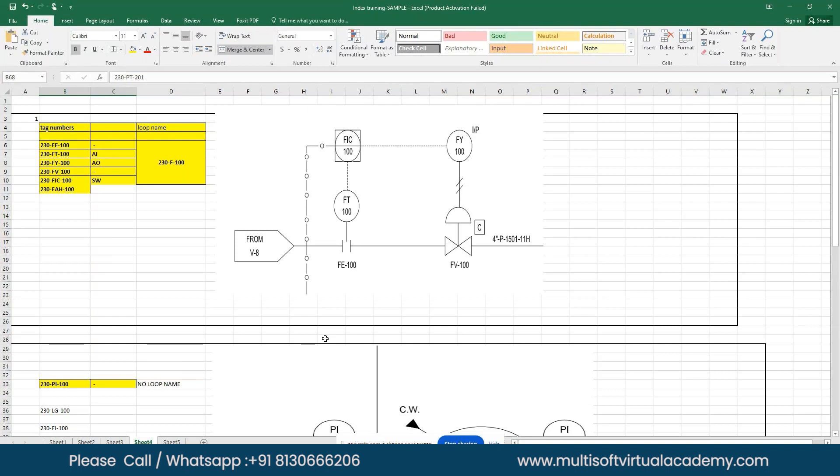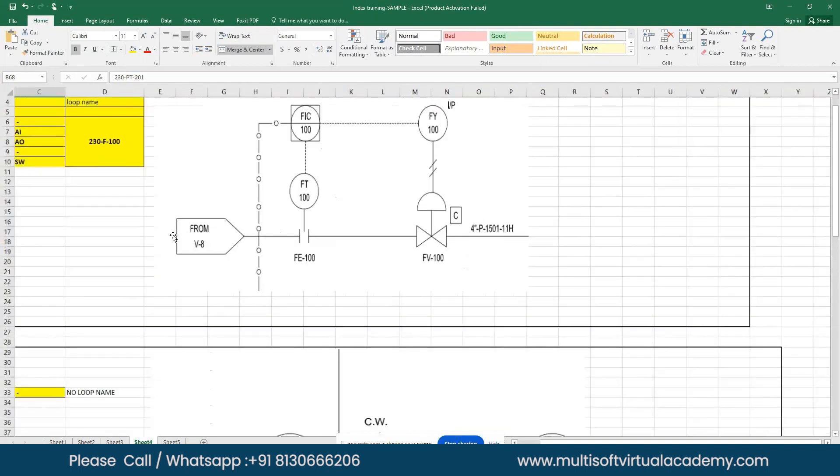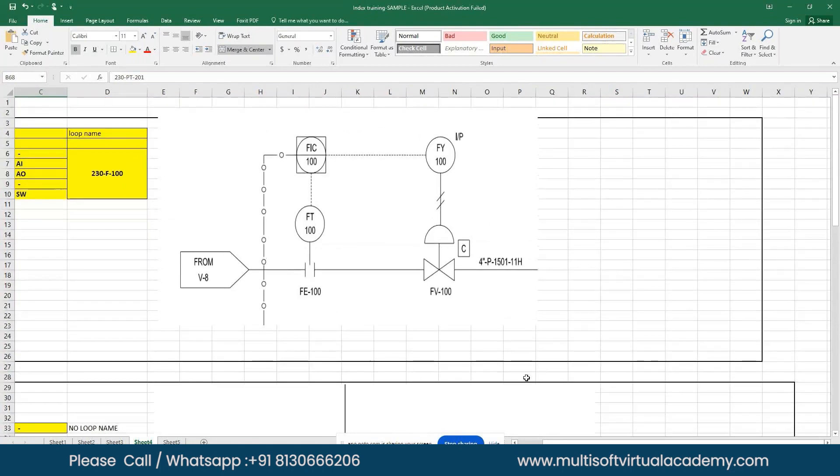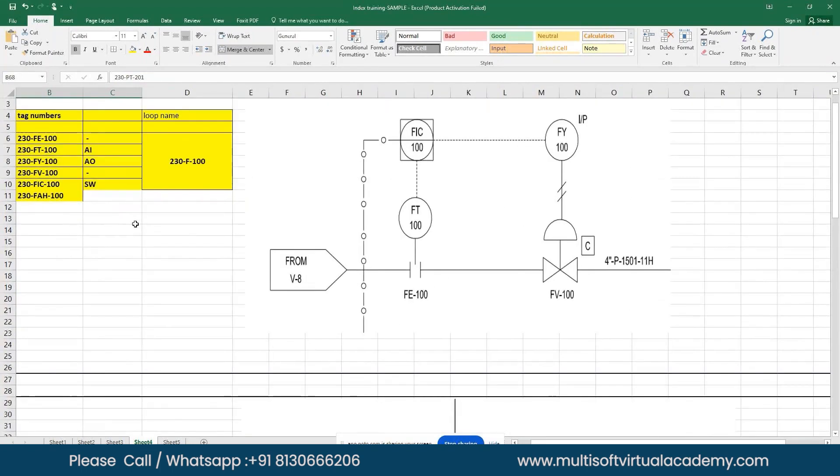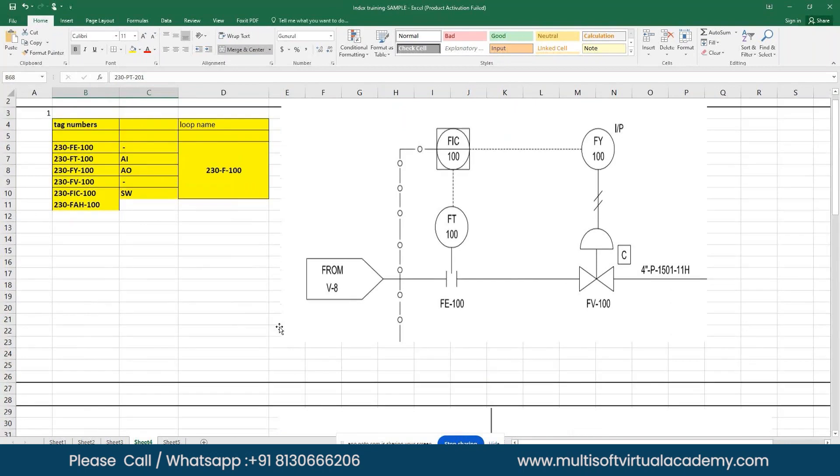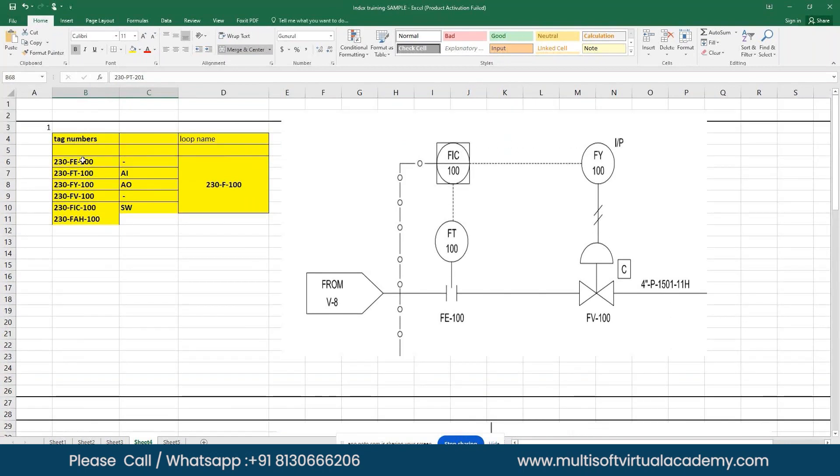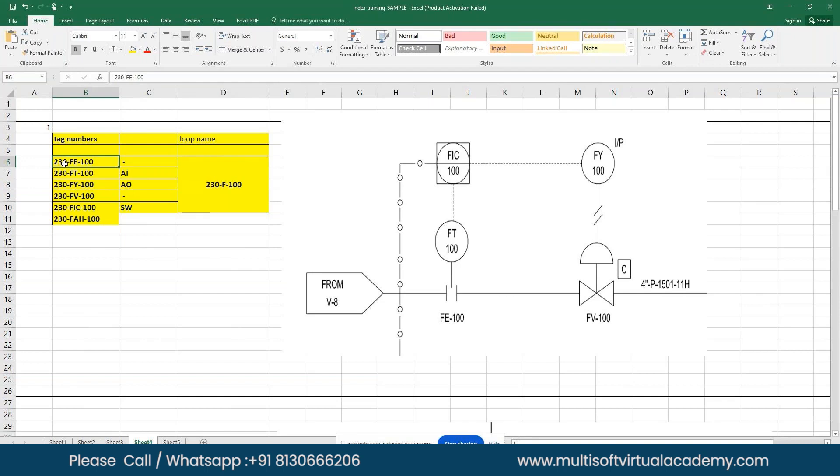This is a sample loop I have shown in this Excel sheet. You can see the closed loop with the tag numbers, the physical tag numbers, and also the soft tags which are FIC. The 230 is the unit number I took as an assumption. FE is the instrument type, 100 is the tag number, and I/O types I have mentioned here.